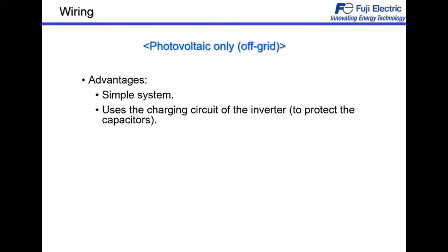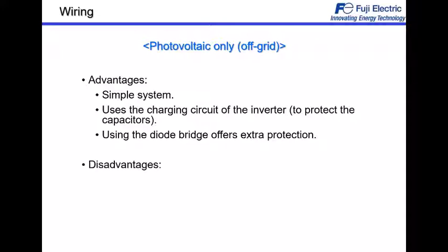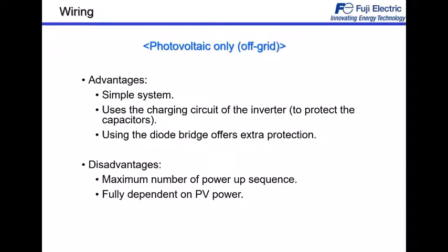Advantages of the system: it is a very simple system. As I have explained before, just one signal can have the system running. It uses the charging circuit of the inverter to protect the capacitors of the inverter. That's the main reason to take the entrance of the inverter. Using the diode bridges offers an extra protection, but it has some disadvantages as well. The maximum number of power-up sequences means an inverter cannot stop many times; it has a limited number of times per hour, because there is a charging circuit and there are some limitations. So that's one of the limitations of this off-grid system. And of course, it is fully dependent on the PV power, on the radiation. If we don't have enough, we cannot pump, and then there is nothing to do.